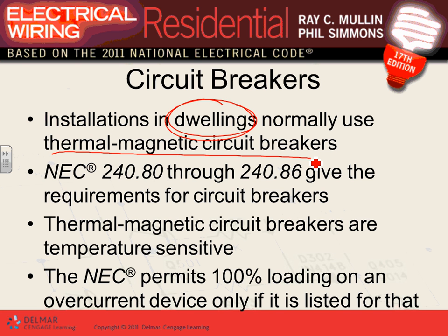Thermomagnetic is the cheapest and easiest. It has a thermal component that heats up and opens — that's overload; and a magnetic component with a coil that sees a huge amount of current and trips for short circuit. That's the most common in dwellings.